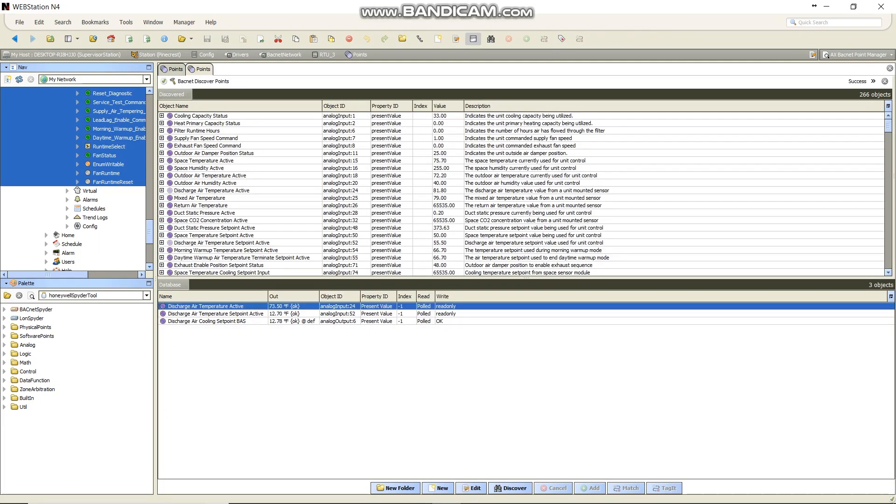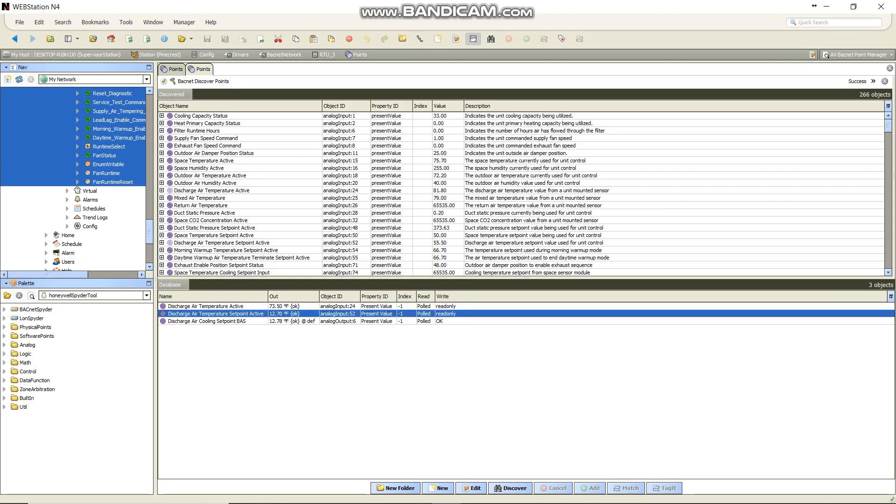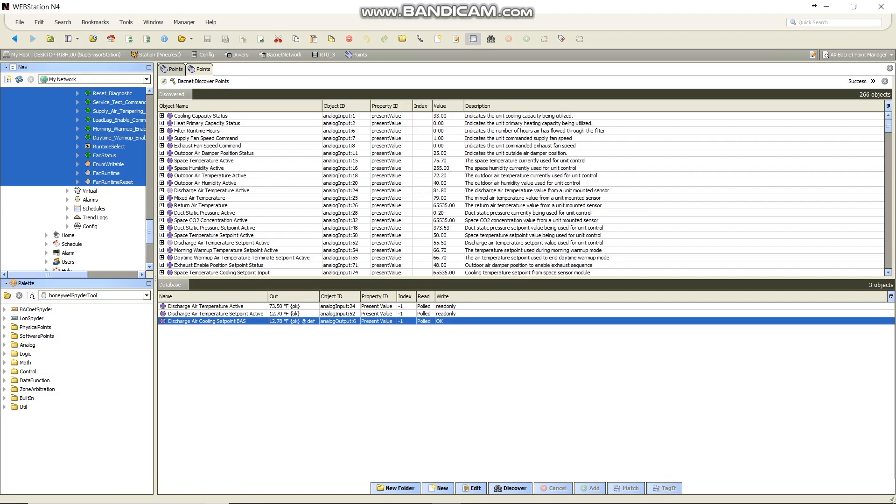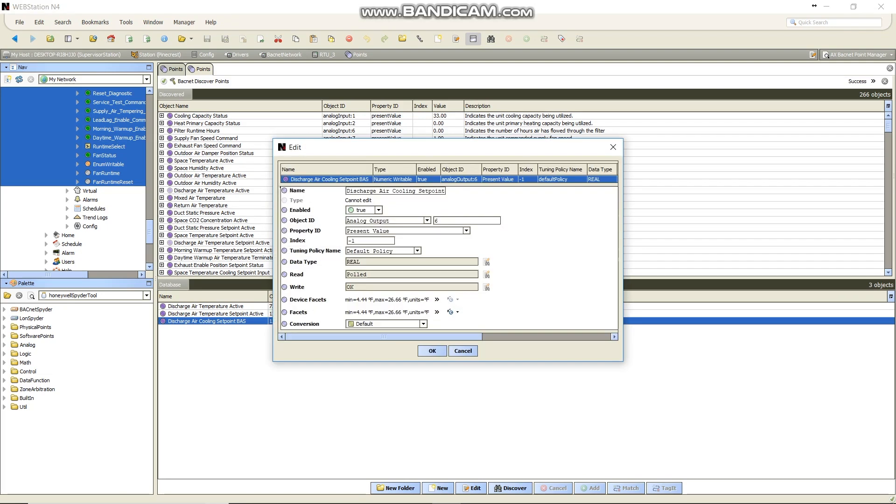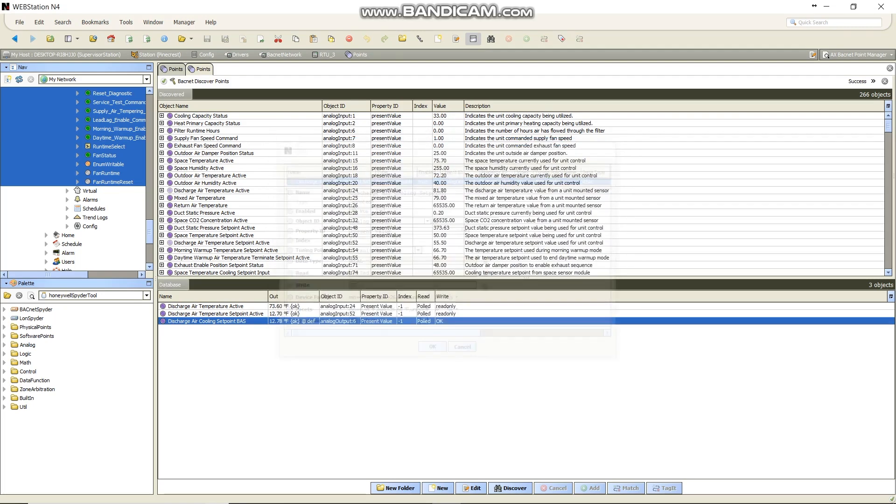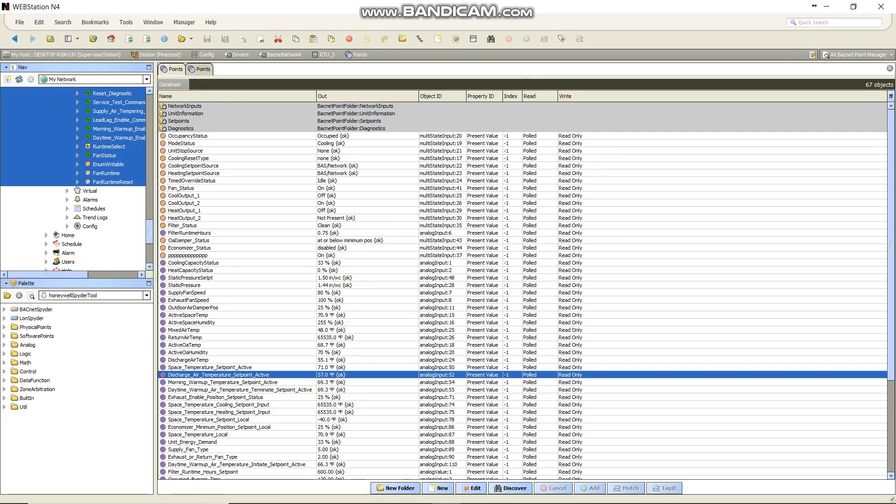That's what we're going to do now. The one we're having issues with is this number three. You can see the discharge air temp looks like a normal reading, but these active setpoints of 12.7 and the setpoint of 12.78 is what's giving me issues. So everything's coming over correct in Fahrenheit, but the problem is the device facets and the facets right here are in Celsius. So I believe, and hopefully, you know, don't call me out too bad if I'm wrong, but 4.4 Celsius should equal about 40 degrees Fahrenheit.